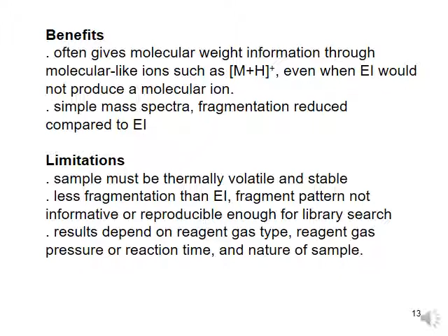And the fragmentation also reduced compared to EI. Now the limitations of this ion source: the sample must be thermally volatile and stable, the same limitation as when you use electron impact. The second point is less fragmentation than EI, so the fragment pattern is not informative or reproducible enough for library search. And the last one is that the results depend on reagent gas type. The reagent must be inert, and the reagent gas pressure or reaction time and nature of the sample are all parameters that need to be controlled when you use a spectrometer.